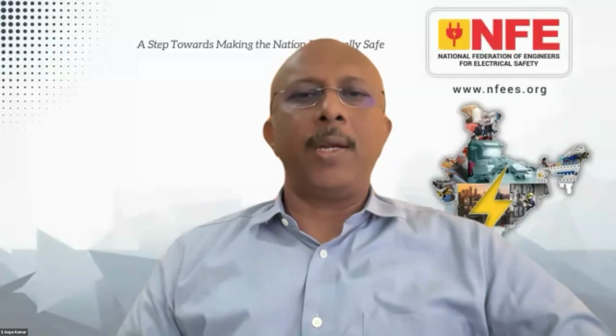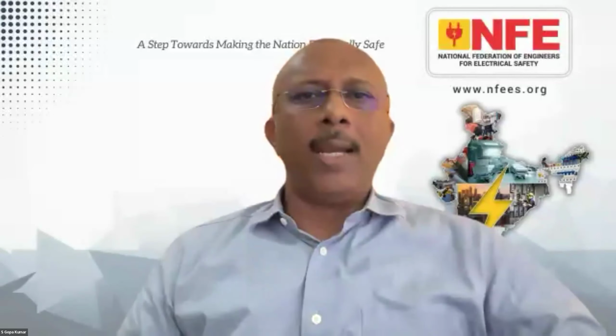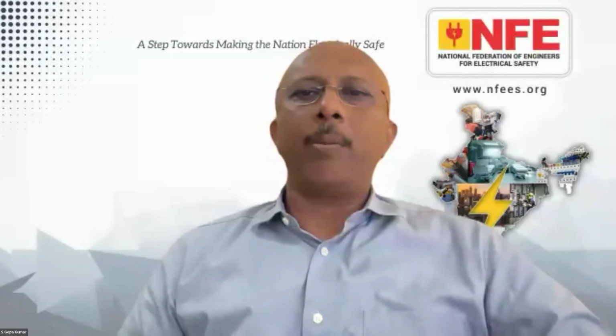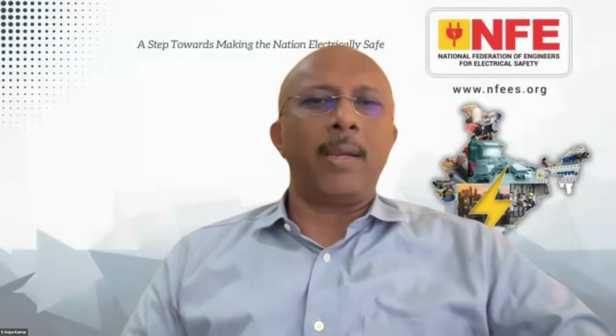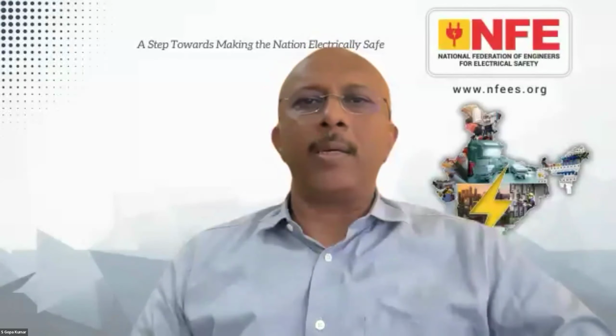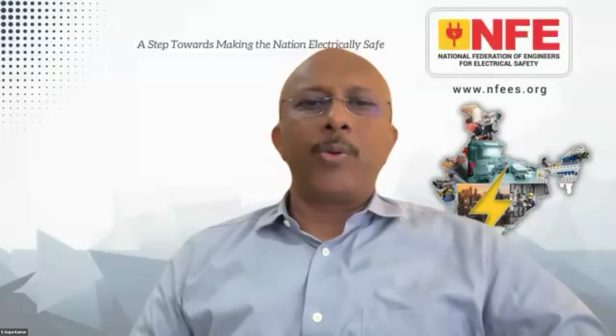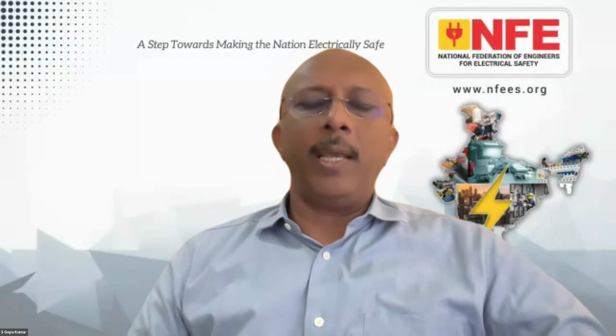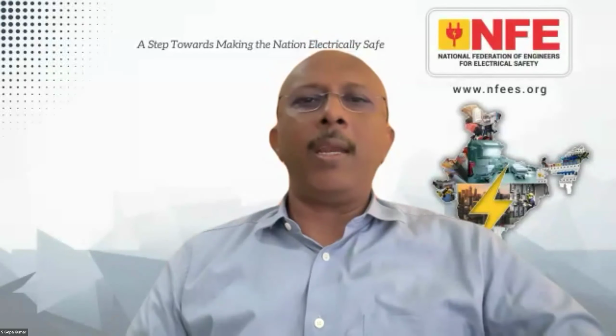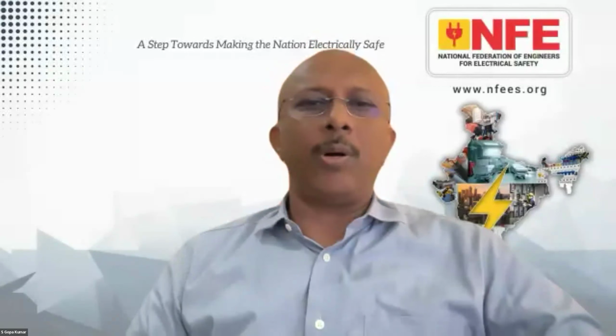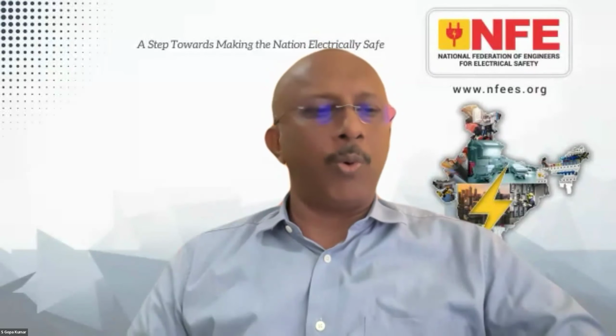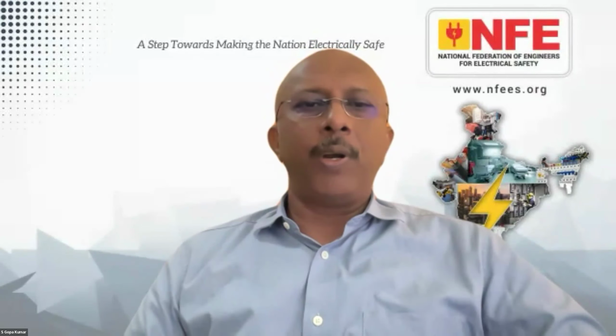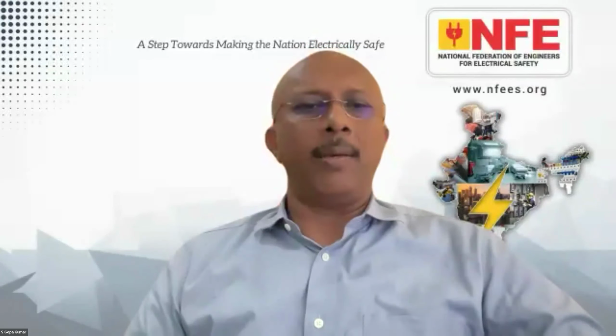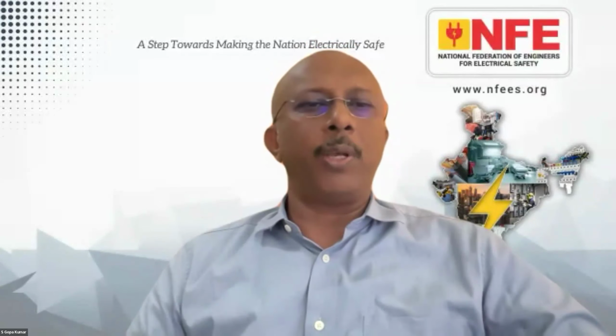Yeah, but Krish, the question is about an installation done during the 90s. So at that time, voltage-based ELCBs may have been used. Anyway, I have no idea. Okay, but the question is whether the device will trip. All kinds of RCDs will trip if the test current is higher. ELCBs, of course, will trip because we are creating a short between the line and the earth. The device makes a short for a few cycles.